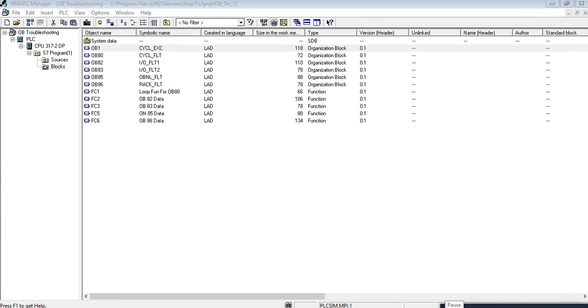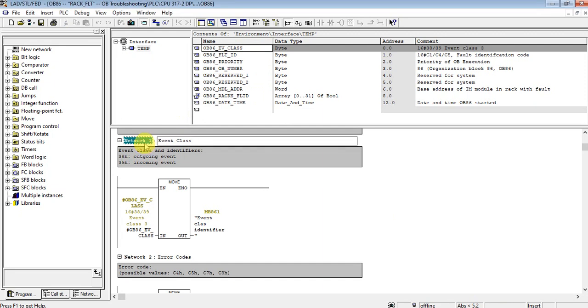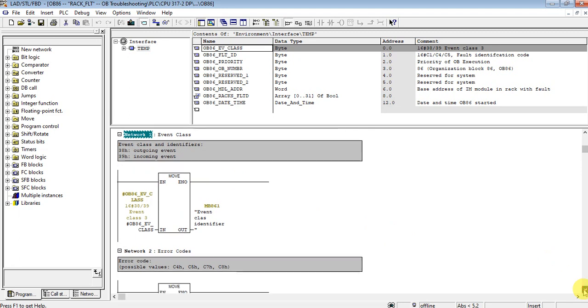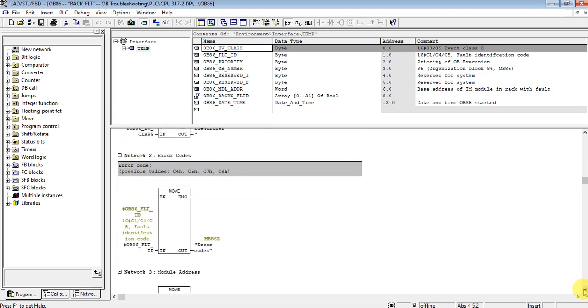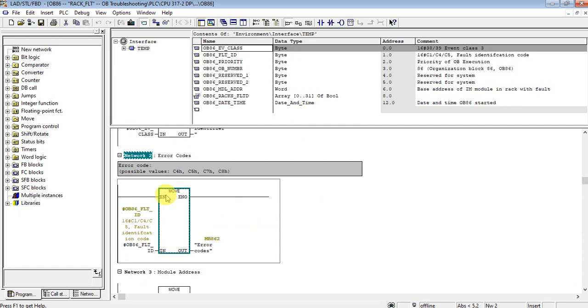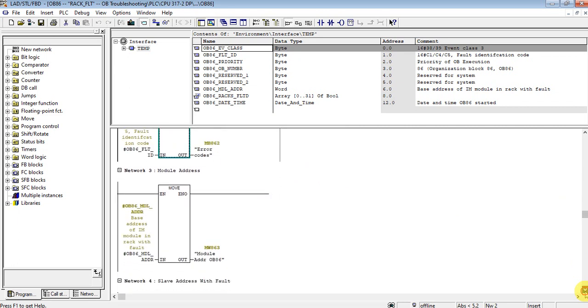Here is OB86 and the default variables are here. Network one, I move the event class here. 38 means outgoing and 39 incoming event. Network two is error codes, as you see we will compare with our PowerPoint later. And network three is module address.